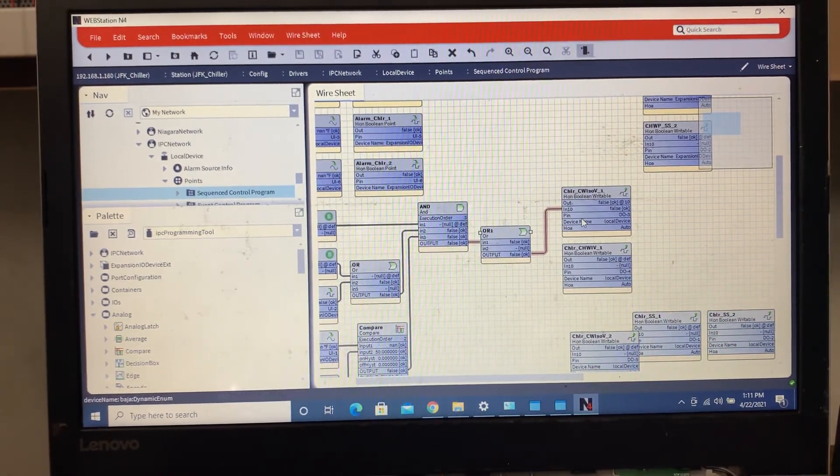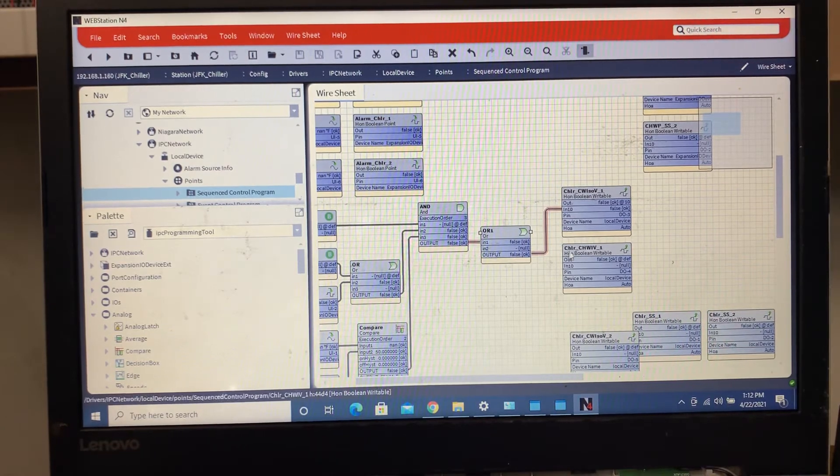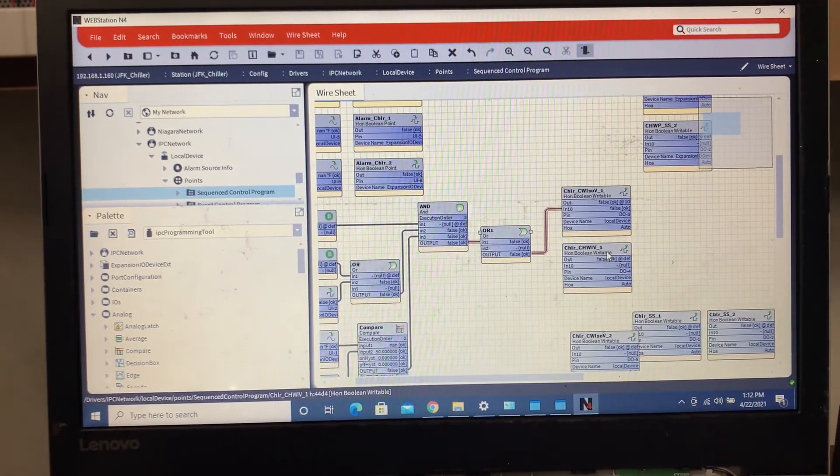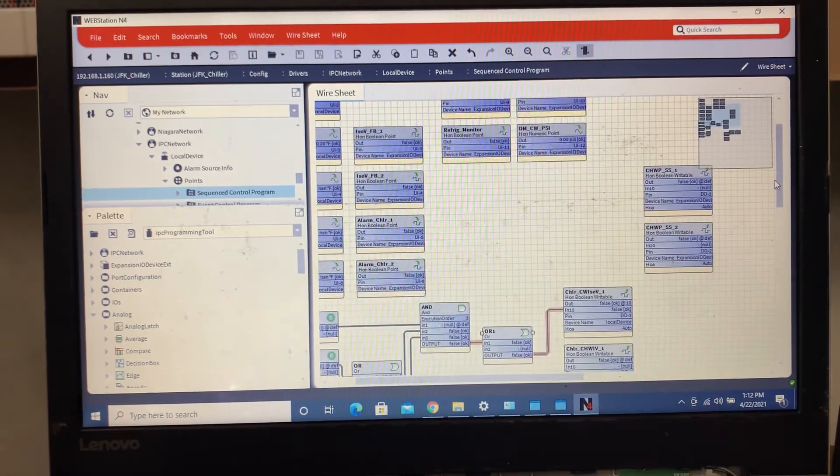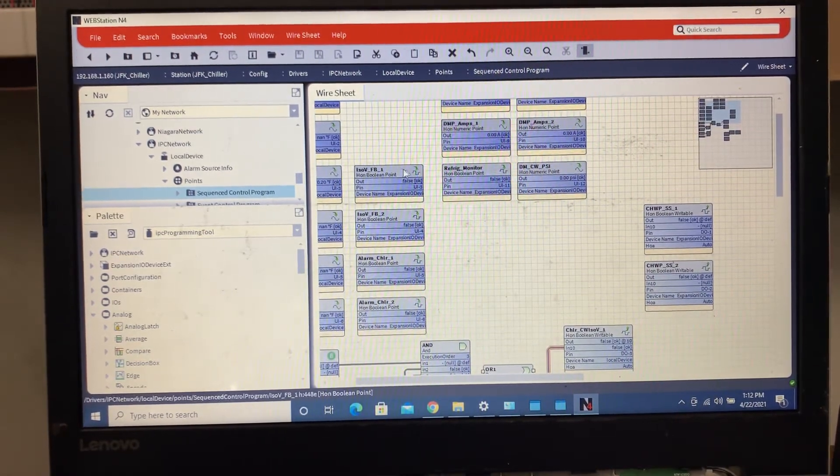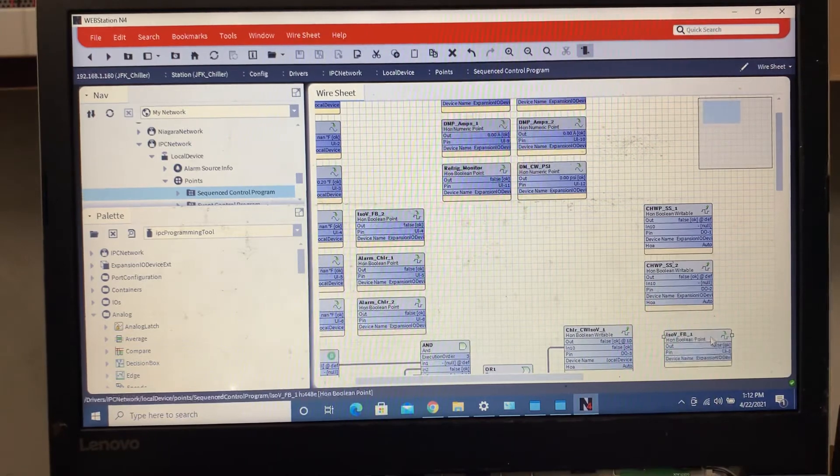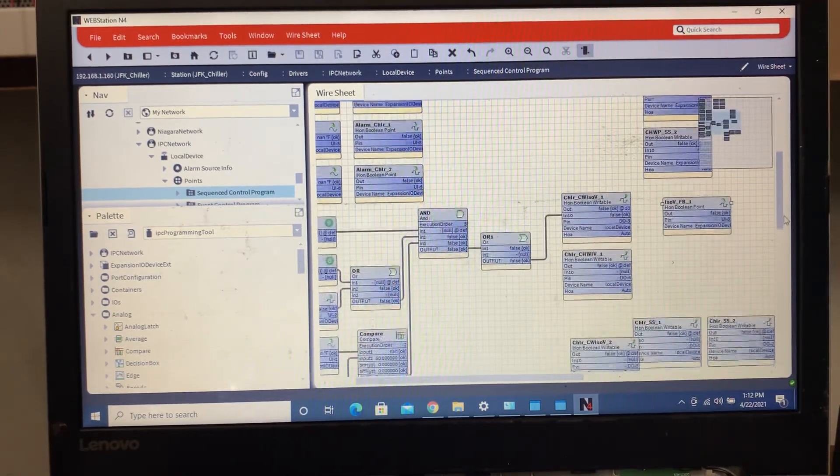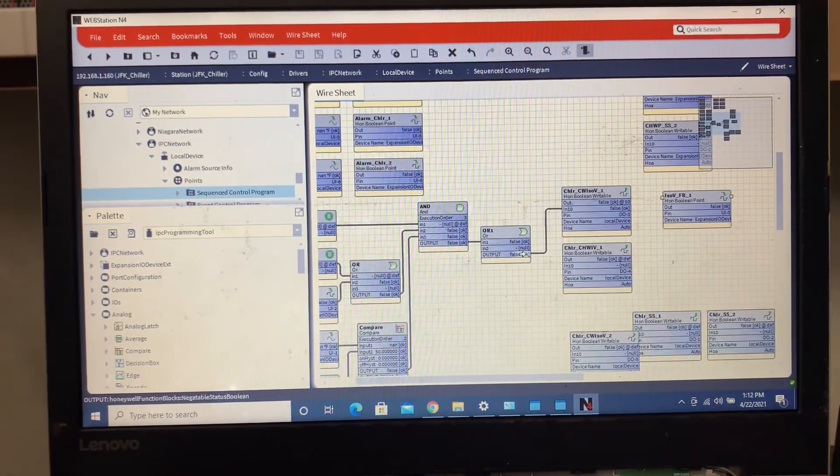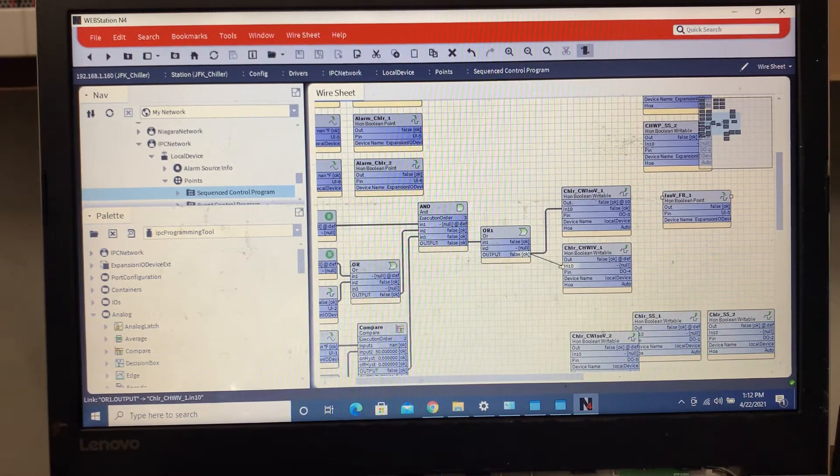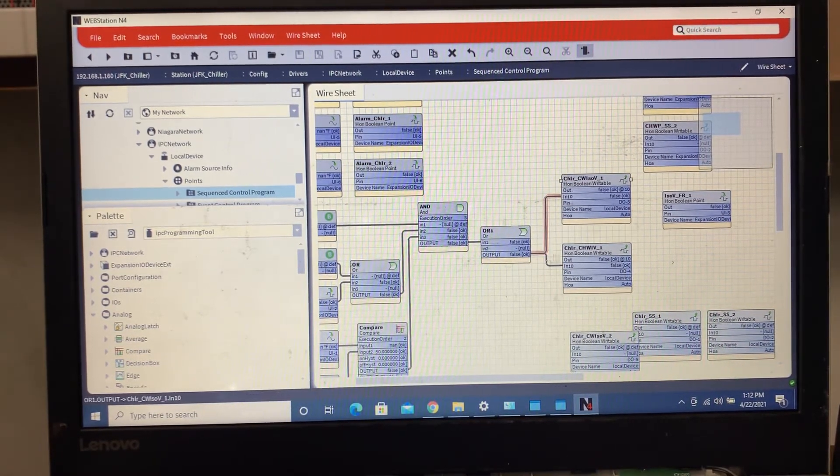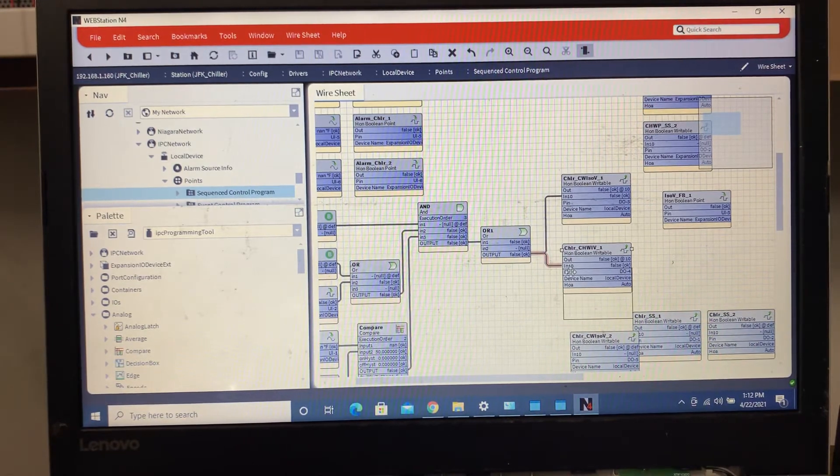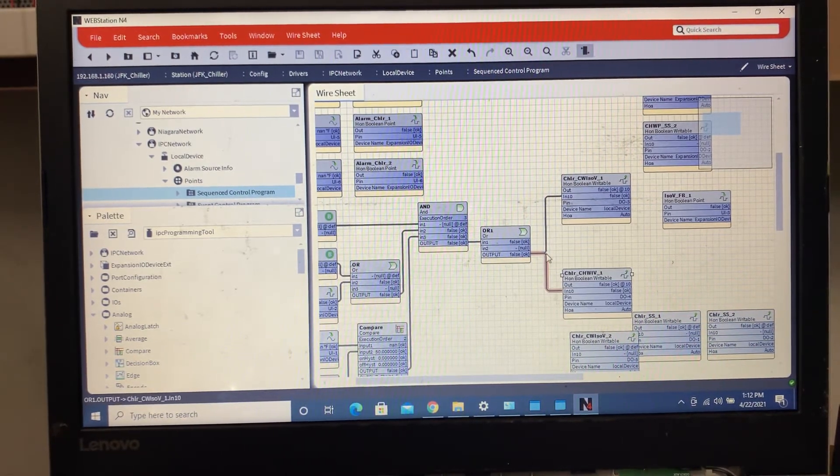We want to do is we're going to open up the condensing water first, then we're going to open up our chill water ISO valve next. Once we open up that, we're going to use this feedback stating that our valve is open. So we're going to say, here so we're going to open up our two valves. I'm going to drop this down, I'll make it look a little bit cleaner in a little bit.